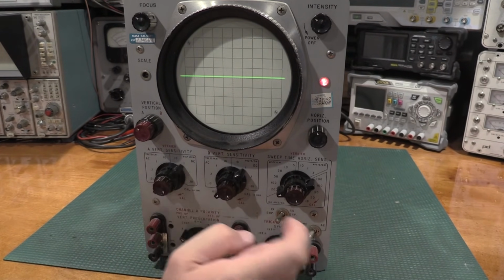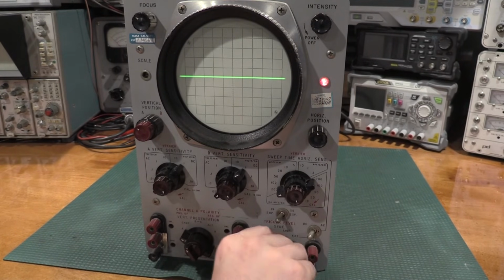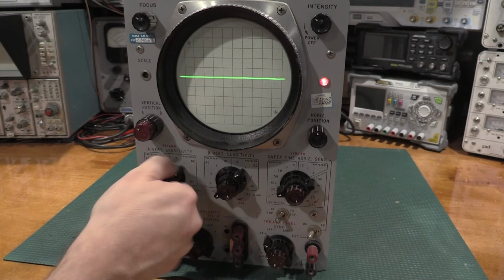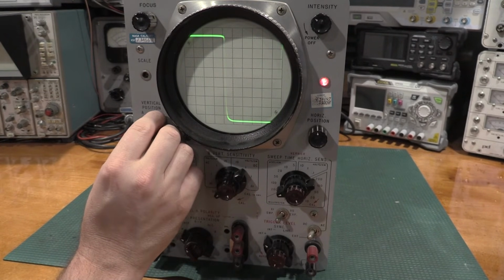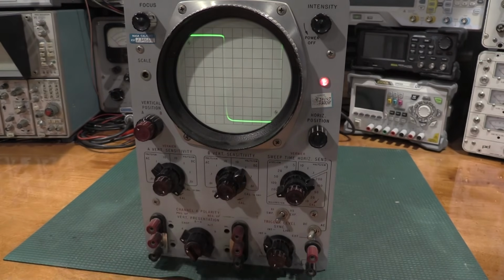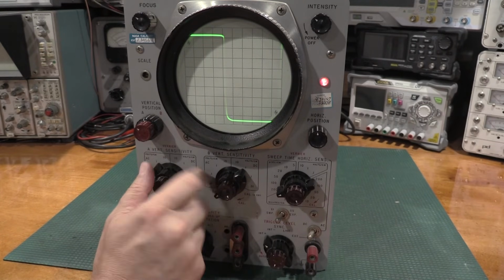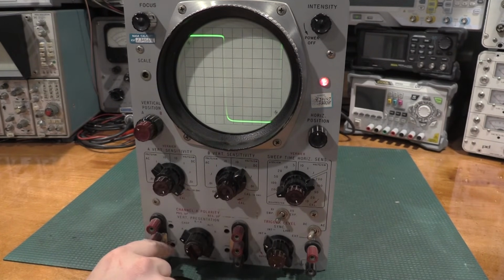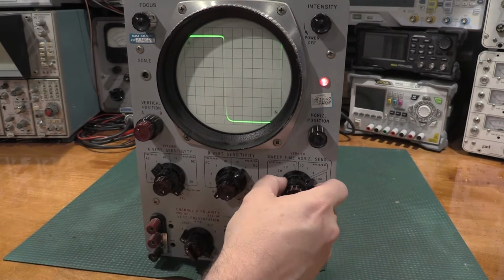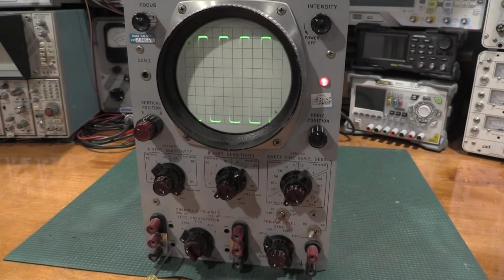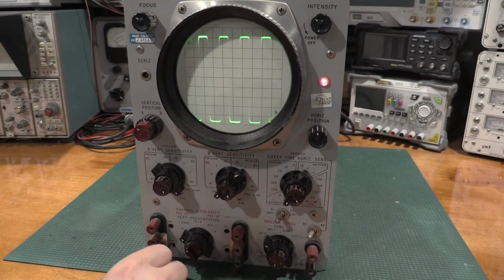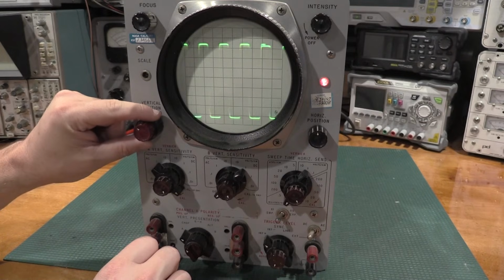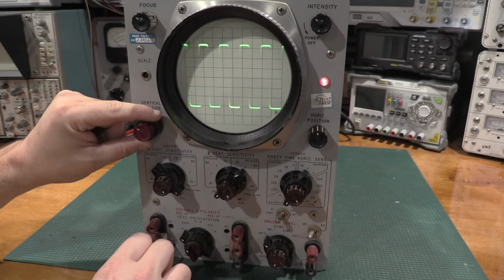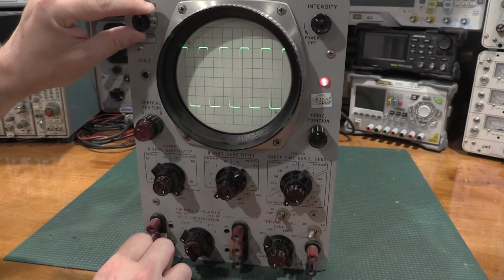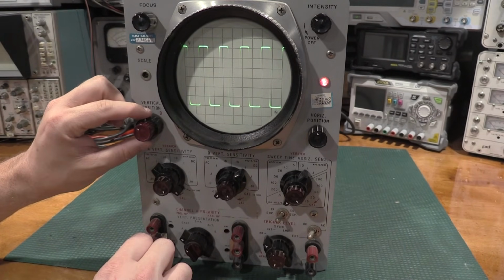Let's see. Channel 1. Internal should be fine. We'll kick this over to the calibrator. Bring this down. Ooh, that's way off. So on the calibration function, at least on this scope, when you take the sensitivity and go all the way clockwise, you should get 6 divisions of display on a square wave. We are getting more than that. So the gain adjust is down here. And let's focus this. Ooh, nice sharp trace. Very nice.